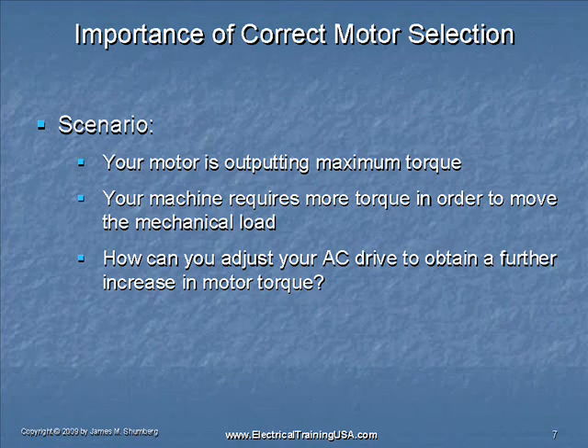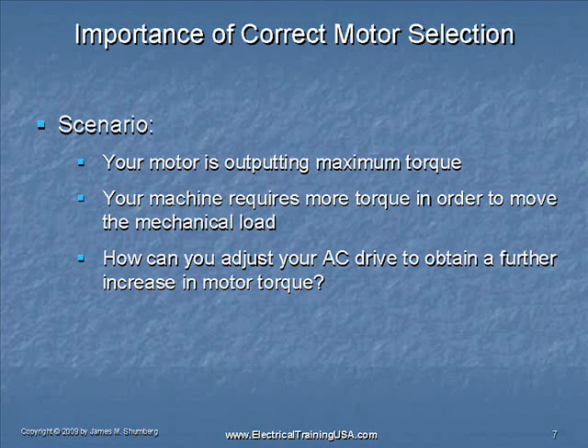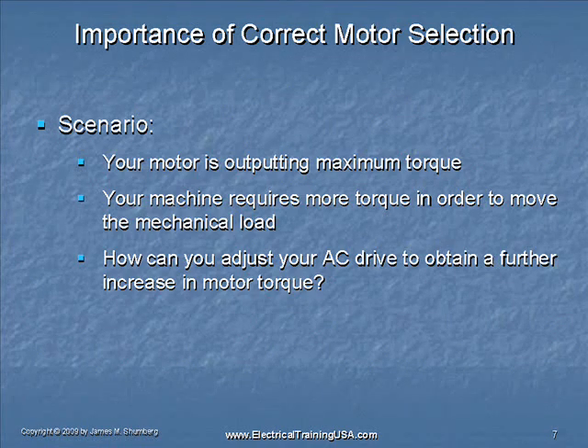Let's suppose that your motor is outputting maximum torque. Let's suppose also that your machine now requires more torque in order to move the mechanical load. Perhaps your owner has decided to add load to the machine — perhaps we want to move a material that's heavier in viscosity, or perhaps we want to add additional load to a conveyor. How can you adjust your AC drive to obtain a further increase in motor torque? Well, if your motor is already outputting maximum torque, you cannot adjust the drive to obtain more torque.